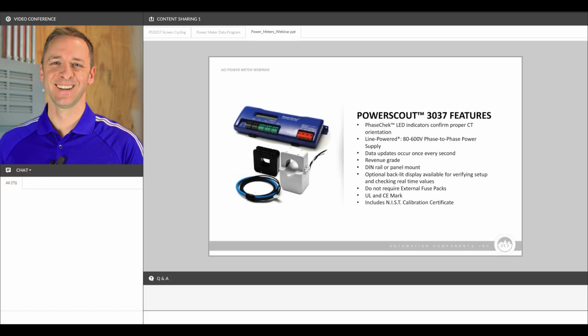It features a phase check LED indication system, and this LED system is unique. It indicates, using the LEDs on the device, whether the CTs are oriented in the proper direction and installed properly. So that helps on installation to make it faster and easier. It's powered by the device or the load being monitored up to 600 volts. So you don't need any external fuse packs with this device. All of the fusing is internal to the enclosure, to the package. So that means fewer devices to install, fewer devices to order.